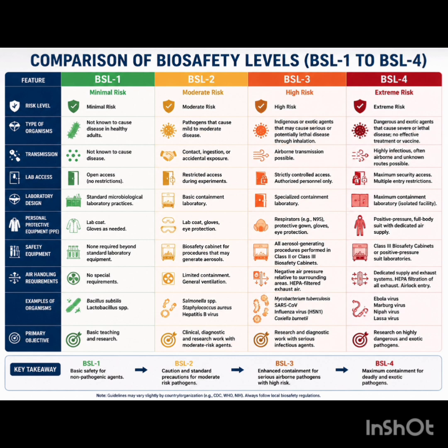As we move higher in the biosafety hierarchy, we reach BSL-3, a level designed for pathogens that can cause serious or potentially fatal diseases and may be transmitted through air. Examples include Mycobacterium tuberculosis, SARS-associated coronavirus, and highly pathogenic influenza virus such as H5N1, because inhalation of airborne microorganisms poses a significant risk. BSL-3 laboratories incorporate advanced engineering controls and containment measures. Access is strictly limited to trained personnel, and all procedures involving infectious materials are performed within biosafety cabinets.